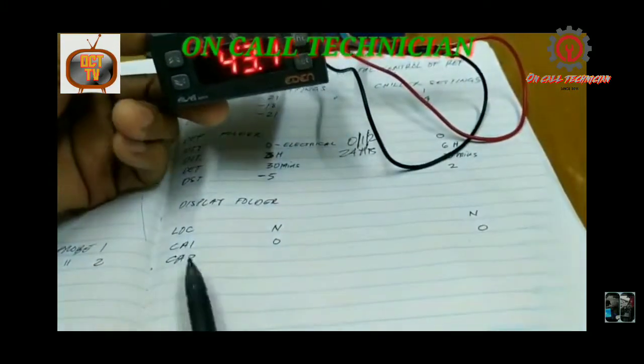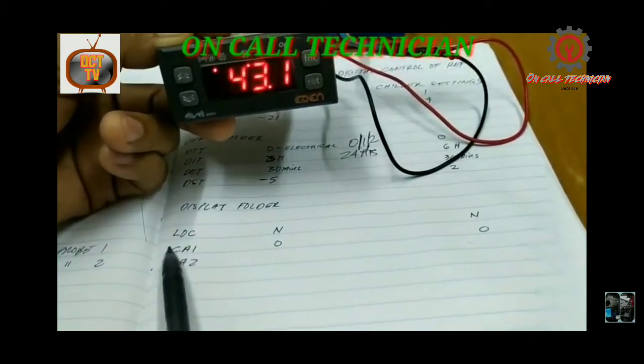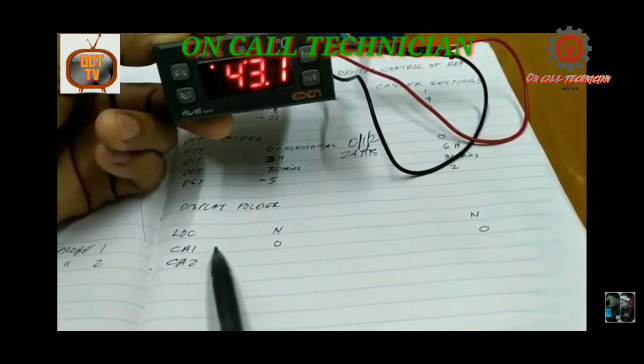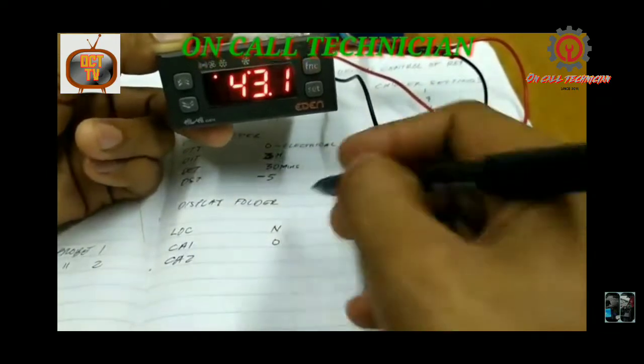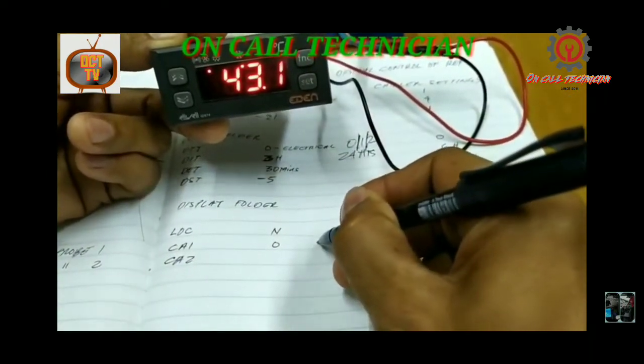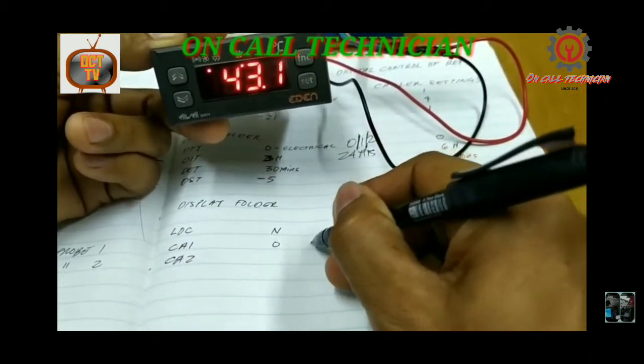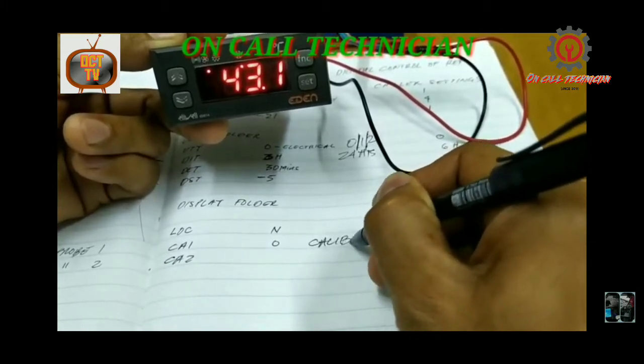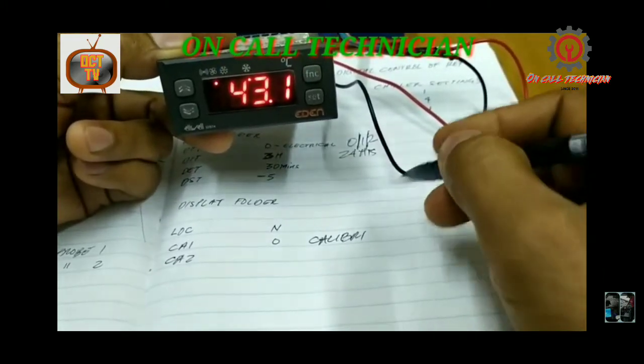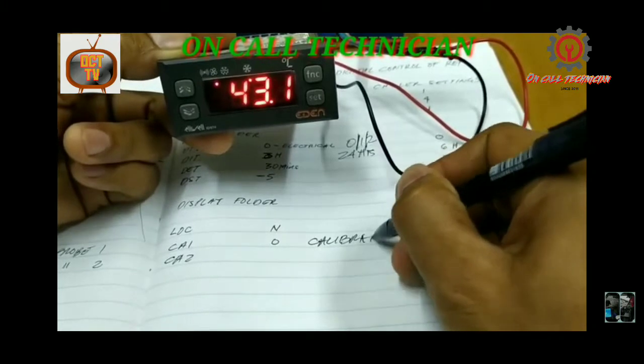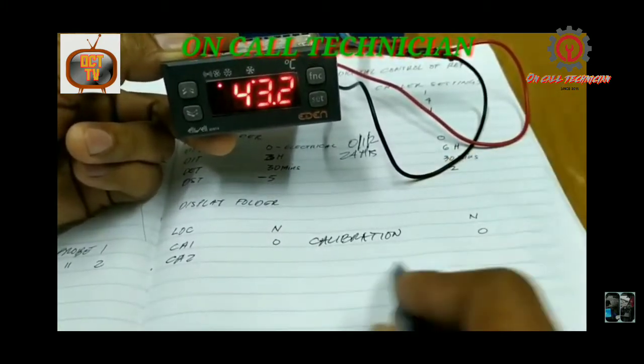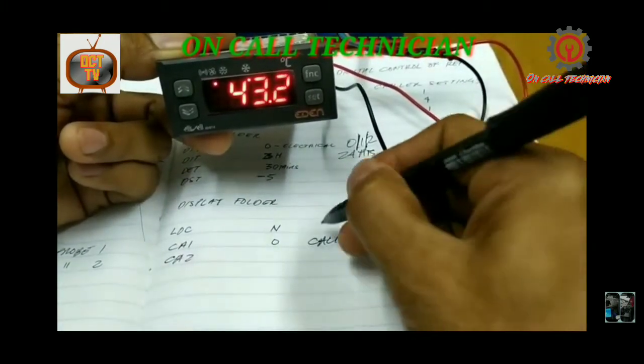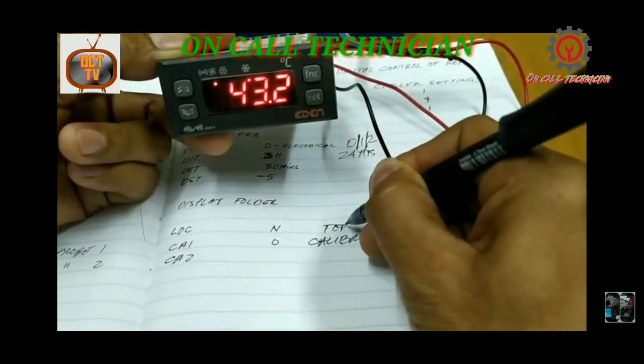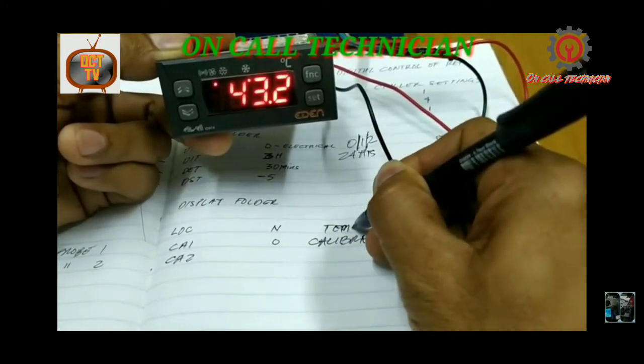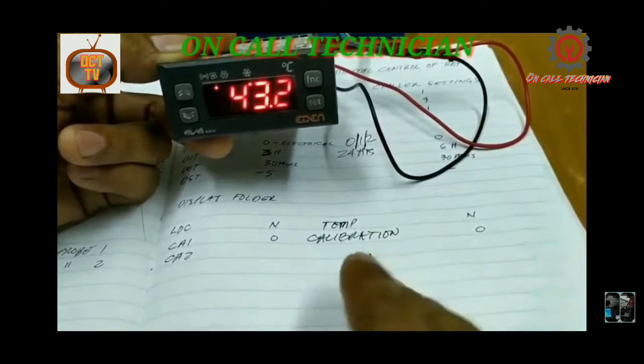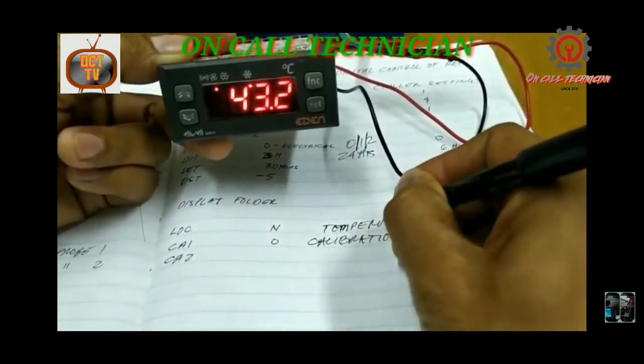Okay, in the chiller it depends on your country, whether you are 1 to 4 or 1 to 10, it depends. So mine is an example only. So CA1, guys, is the calibration. CA1 is calibration under the display folder. So this is temperature calibration.